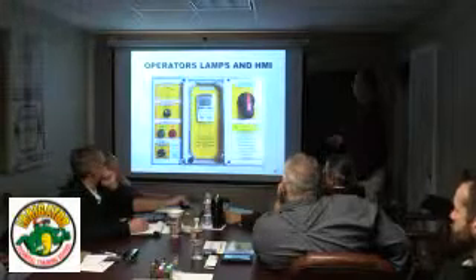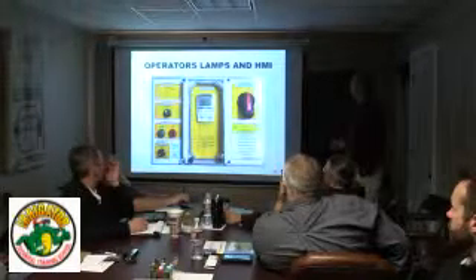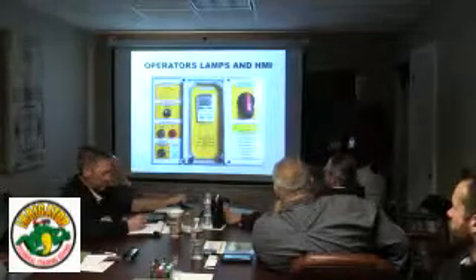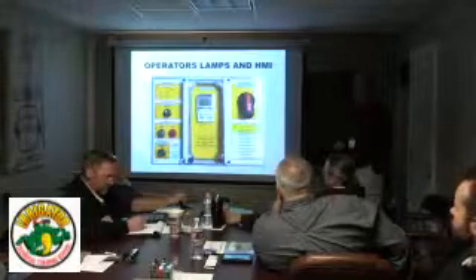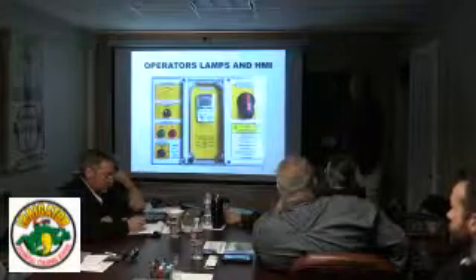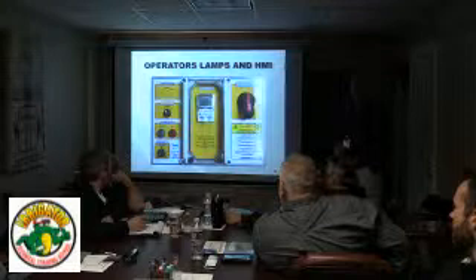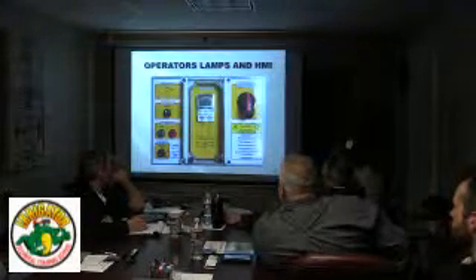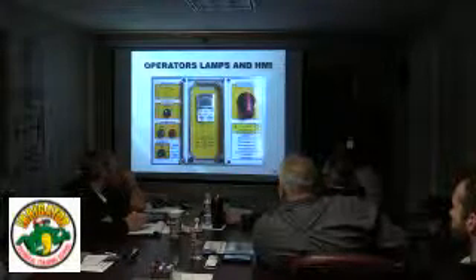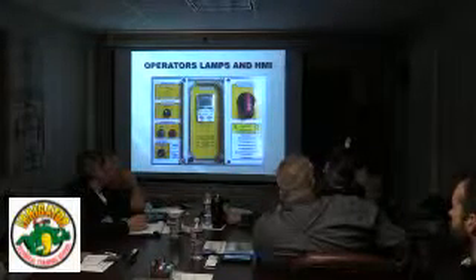All of our panels are going to have basically at least what we call an HOA, a hand-off-auto. So in auto, it's going to run under pressure mode. It's going to try to maintain a constant pressure, whatever pressure you tell it to maintain. So that's in the auto mode. This manual speed control down here doesn't do anything when it's in auto. The drive doesn't even look at it, so it doesn't matter where that's cranked when you're in auto. It's just going to run in auto in PID mode, which is maintaining a constant pressure.